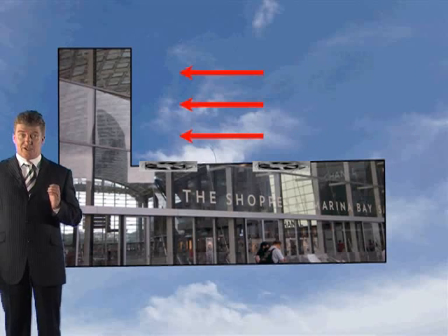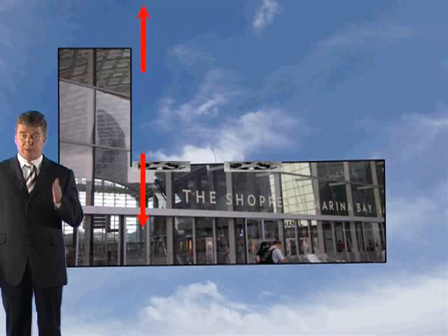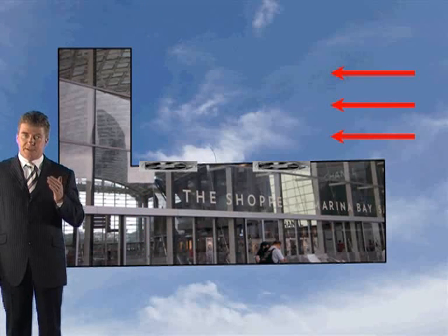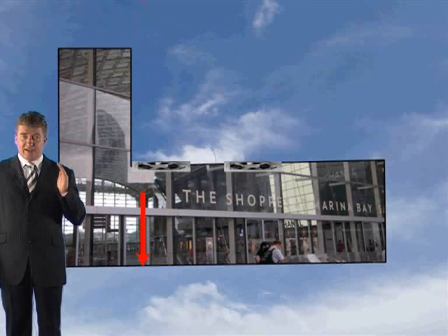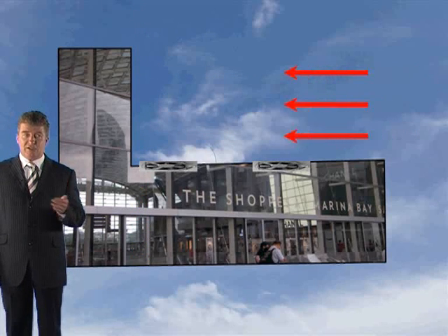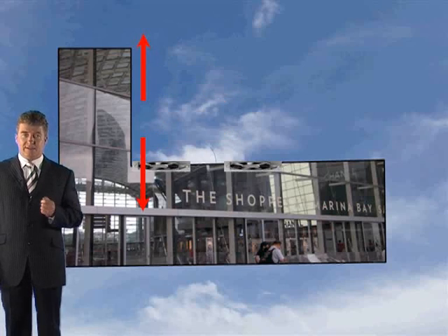Now let's look at the potential problems that you may encounter. All natural ventilators have the same potential problem, as their performance can easily be affected by adverse weather conditions. This is especially the case when back pressure is generated by surrounding buildings. As you can see here, if wind hits a taller building adjacent to the roof of the building where the natural ventilators are going to be fitted, then you will get a back pressure. This will adversely affect the ventilator's effectiveness.